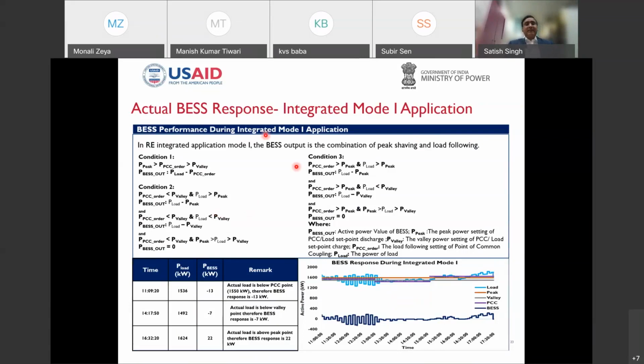So we have clubbed the first 2 applications, peak shaving and load following. Here there would be 3 set points. In peak shaving we had 2 set points, the upper and lower band, and in load following we had a fixed 1 set point. Here, by one battery with loop, if my fixed set point for load following is between the band of peak shaving, the battery would try to maintain the fixed point for the load following application. But whenever that deviation is beyond the band, it will go back and toggle to the peak shaving application. So the same battery, configured and deployed, would function in both modes so as to maximize the overall benefit from the same unit.